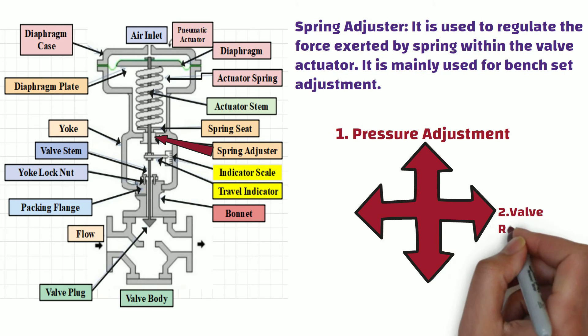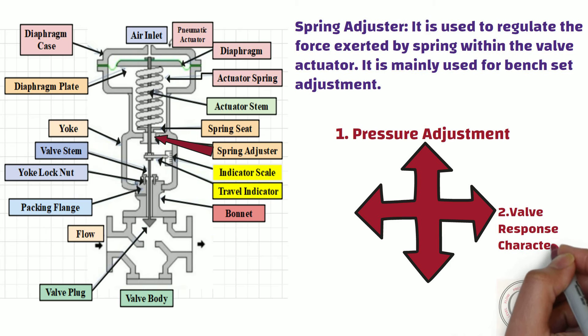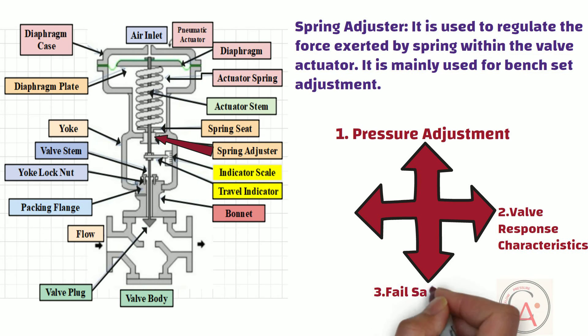Secondly, it can be used for fine-tuning the valve response characteristics to meet the process requirement. It can also be helpful as a fail-safe mechanism. If there is a loss of pneumatic pressure or control signal, the spring returns the valve to a predefined position, usually fully open, fully closed, or some intermediate position. Adjusting the spring tension can determine the fail-safe position of the valve in case of actuator failure or loss of control signal.